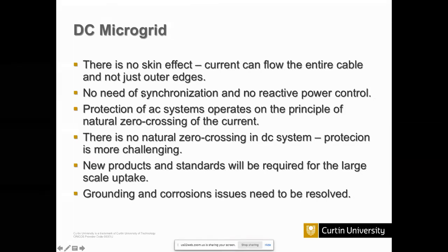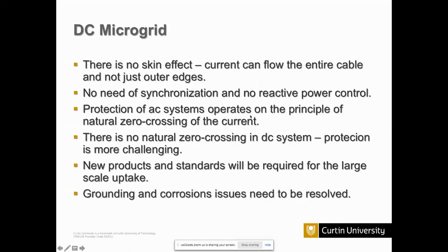However, AC systems score in one aspect. The protection of AC systems operates on the principle of natural zero crossing of the current. This means when there is a fault, you want to open the breaker while your current is still sinusoidal, so you look at the natural zero crossing of the current and open your breaker at that time. There is still flashover, but you have a very good chance of extinguishing the fault current while you separate at the natural zero crossing.